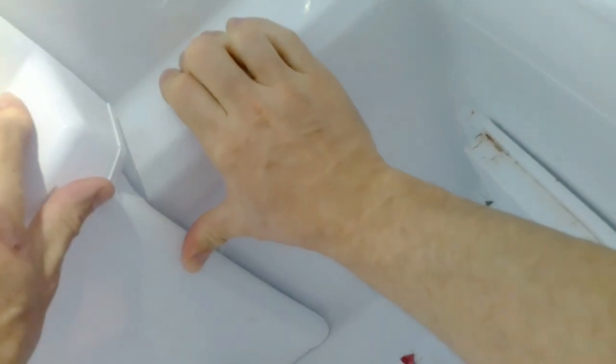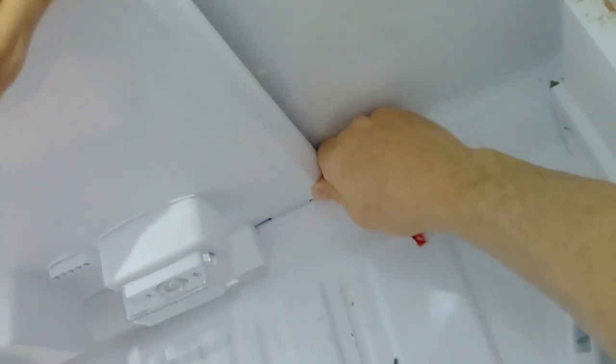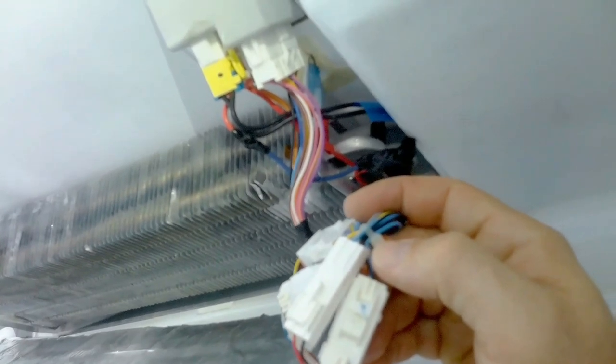What we're going to do is take this back off and then tuck it. But if you look here on the right, it has a big gap. That big gap could be a problem because that evaporator will basically absorb the heat and cause a big ice effect and restrict the air flow. Let's take this back off and see if we can tape these wires into place where they're not just all over the place. I don't know if this was done because someone's worked on it before and pulled them out of the housing.